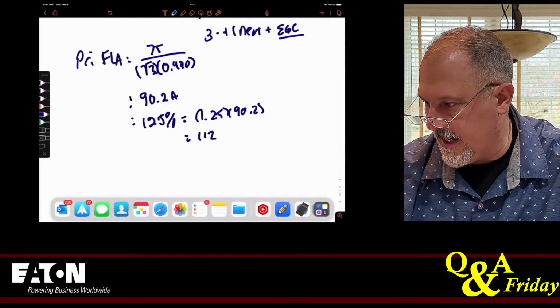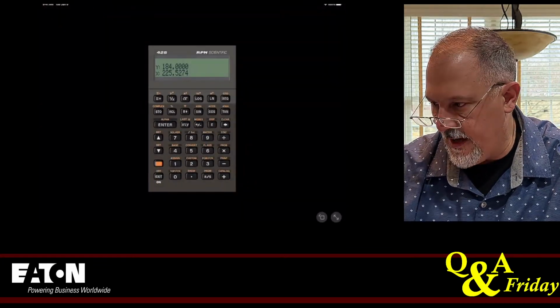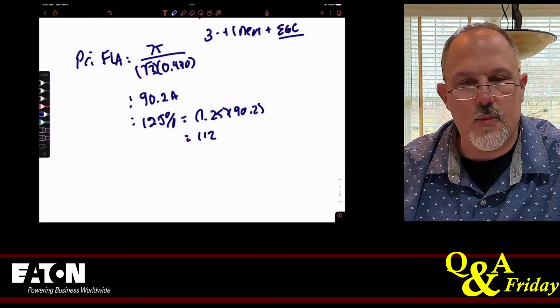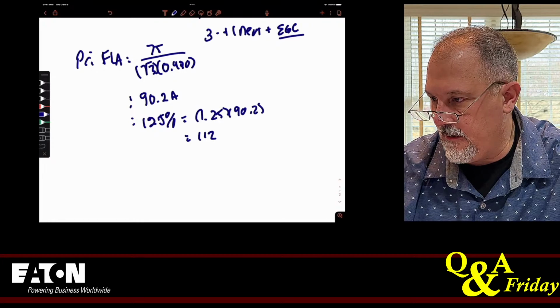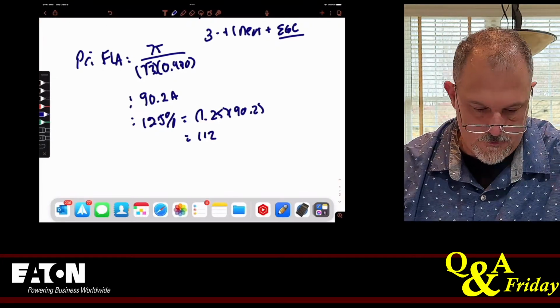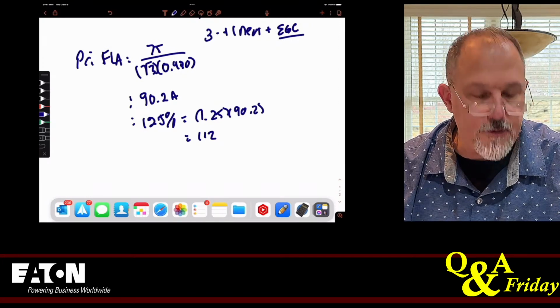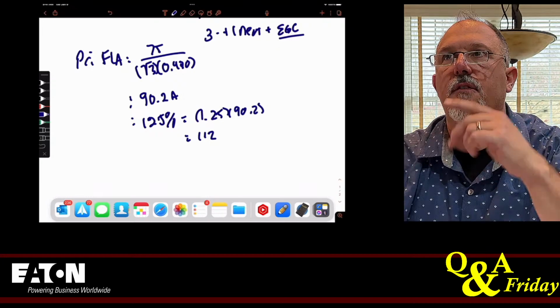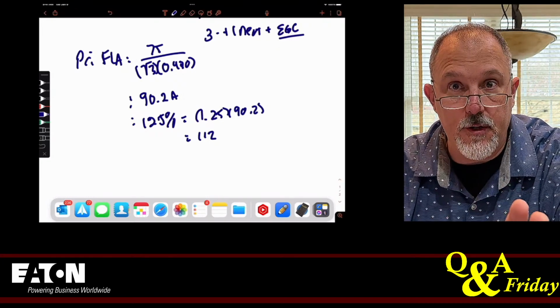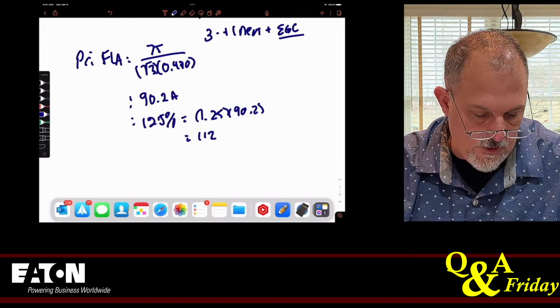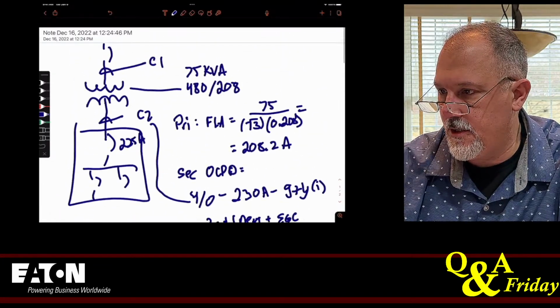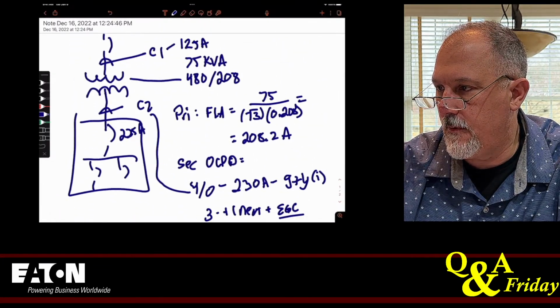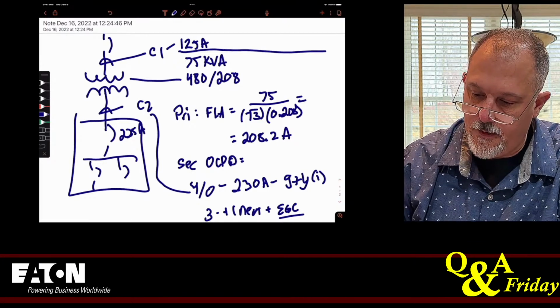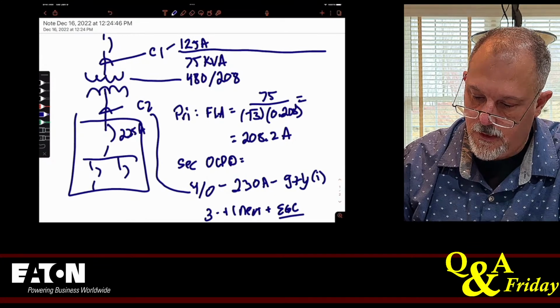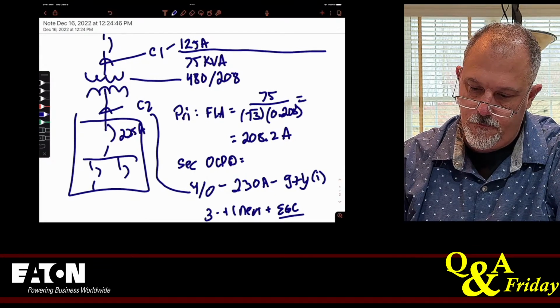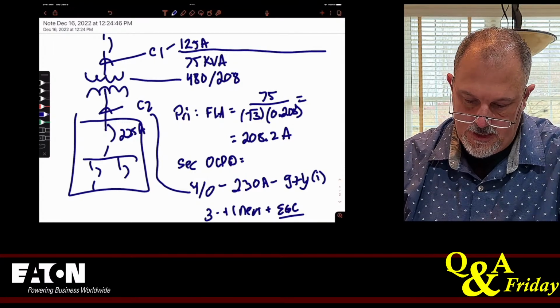So what do we say? If the highest I can go on the primary is 225 and my 112 amps is 1.25, I could put a 150 amp breaker there, or I could put a 175, I could put a 200. What would govern why I would pick? I would probably want to pick the smallest breaker I could. That would give me the lowest cost. So if I did 125 amps on the primary, I'd need 125 amps worth of conductor, and then I go to 310.16.